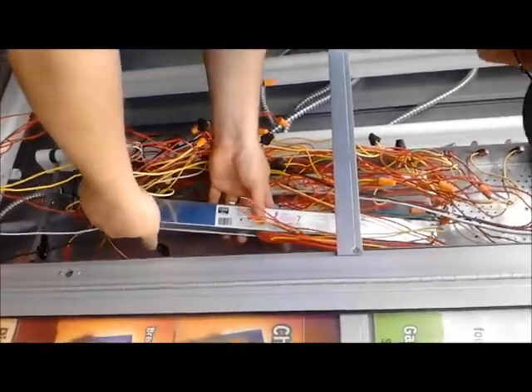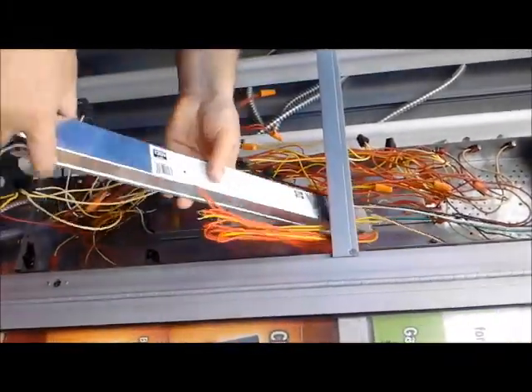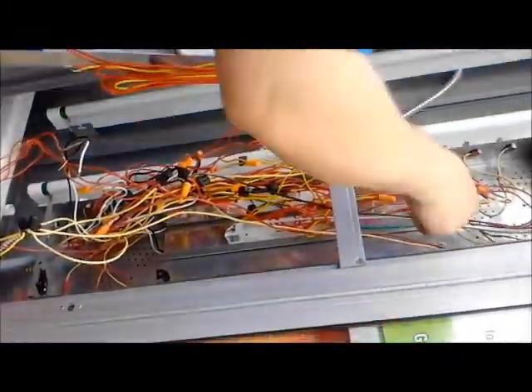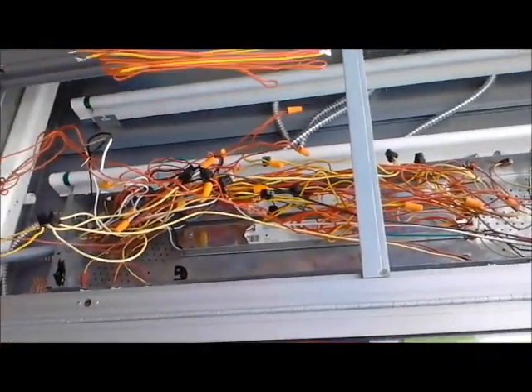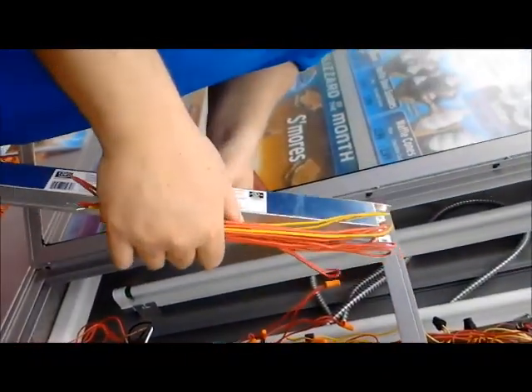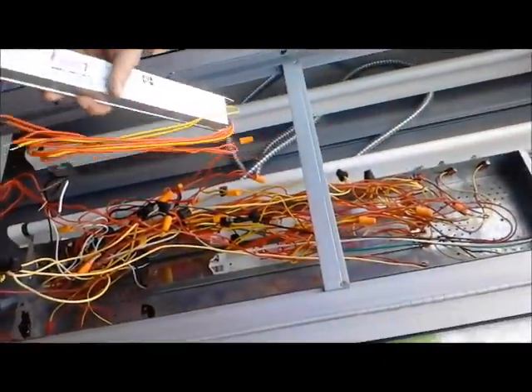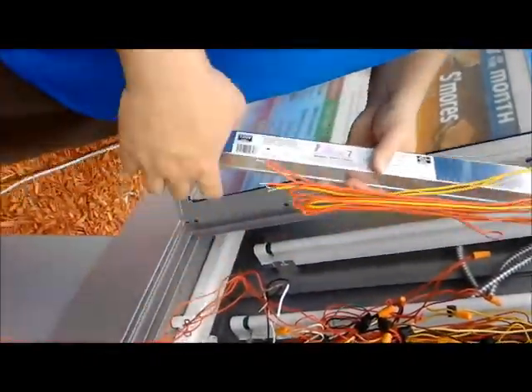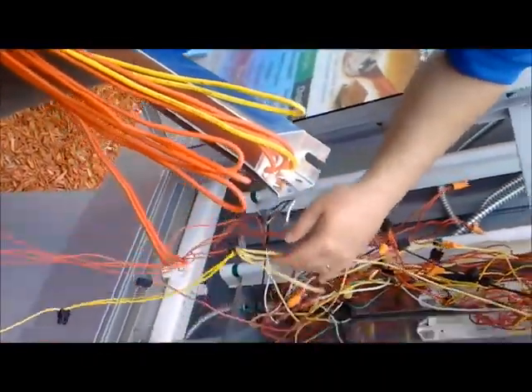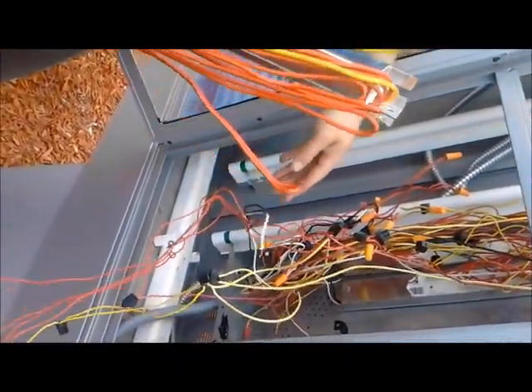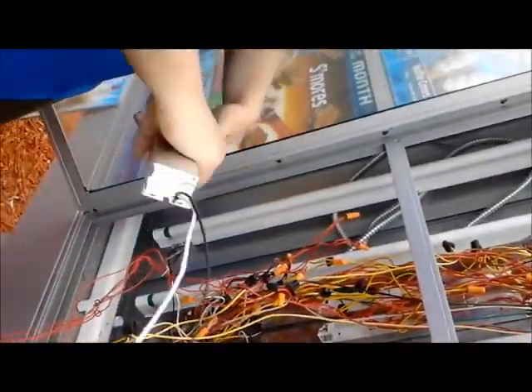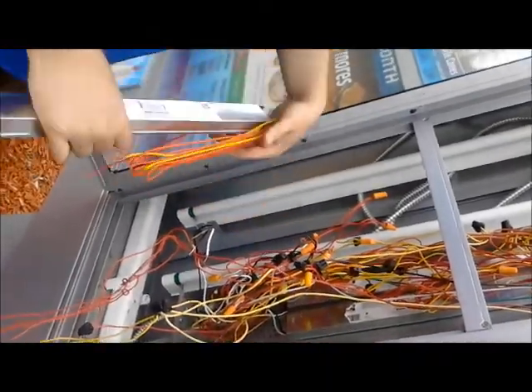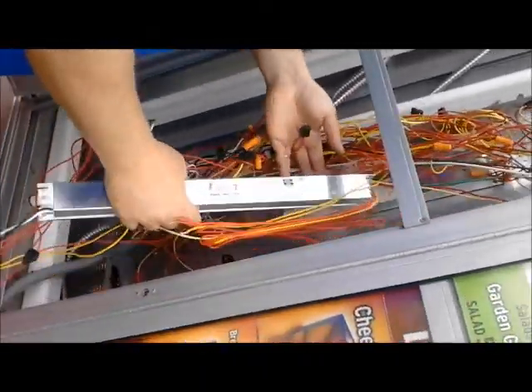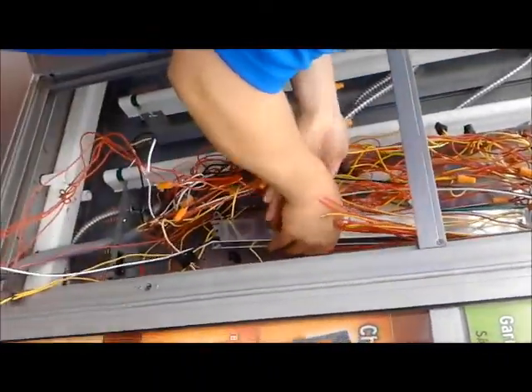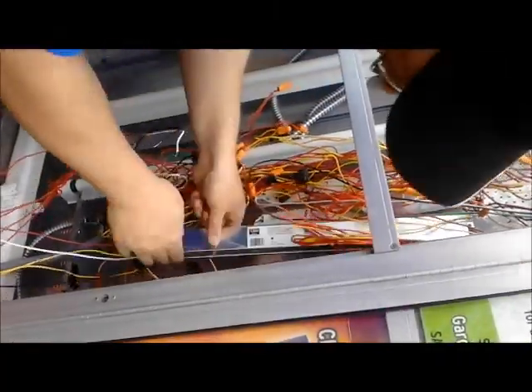Now what we're going to do is slide this ballast in. We're going to slide it into the bolt that we can't get out, and then we're going to put the bottom bolt back in. But you need to have the red and yellow wiring facing towards the top and the black and white wiring facing towards the bottom. That's just because the power wiring is down here. If you flipped it around, there's just no way you're going to get the power wires to hook up. So make sure the red and yellow wiring is on top.